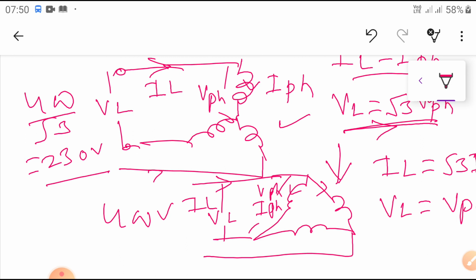Okay, so once the speed of the rotor increases to 85% of the rated speed, then we move from star to delta with the help of some mechanism. Then we apply 400 volts continuously, in such a way that we protect our motor by initially reducing the voltage. So how are we going to provide overload and no-load protection? Similarly, by using the OLR and NLR coils connected in the circuit. Okay, so this is the basic concept of the star delta starter.